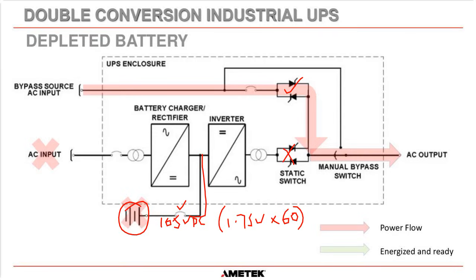Now at this point, you are on bypass through the static switch. Remember the difference between static and manual switch. A manual switch is mechanical. A static switch uses these SCRs. So it's an automatic transfer, seamless, without any issues whatsoever. It was make before break, and that takes care of the loads when the battery is depleted.